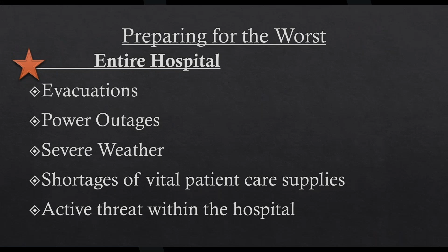If you do have sterilizers in your scope of service, they are one of the most critical pieces of equipment to the operating rooms, and the operating rooms cannot function properly until the machine is fixed. Life support equipment is categorized as ventilators, anesthesia machines, dialysis machines, defibrillators, infusion pumps, patient monitors, pacemaker programmers, oxygen concentrators, nebulizers, just to name a few. And you will notice that closing out these work orders and ordering parts and the turnover time to repair these devices will look different. These devices are the most common.